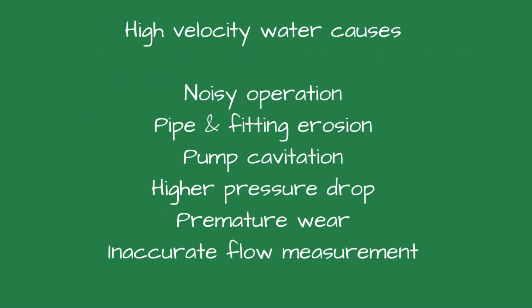What are the problems you get with high velocity? High velocity water creates turbulent flow which results in whooshing, rattling, and knocking sounds, especially near fittings, valves, or small diameter pipe. Sudden changes in direction or pressure can cause water hammer, which damages pipes and annoys building occupants. Fast-moving water, especially in copper or brass piping, can gradually erode the inner walls of the elbows, T's, and valves. Over time, this leads to pinhole leaks, premature pipe failures, and costly repairs.